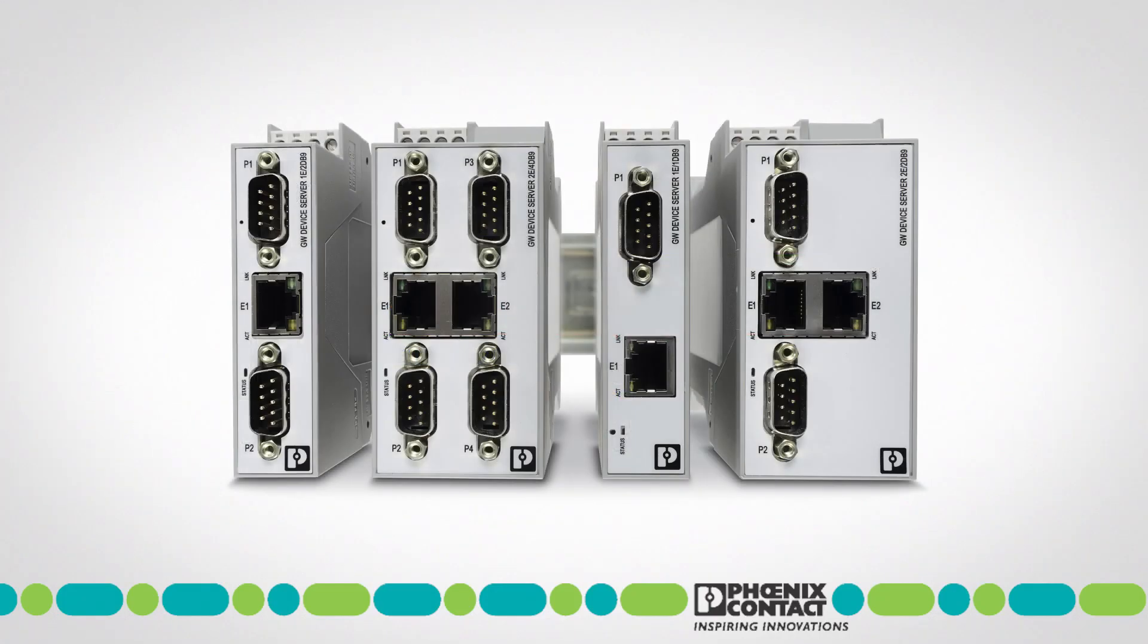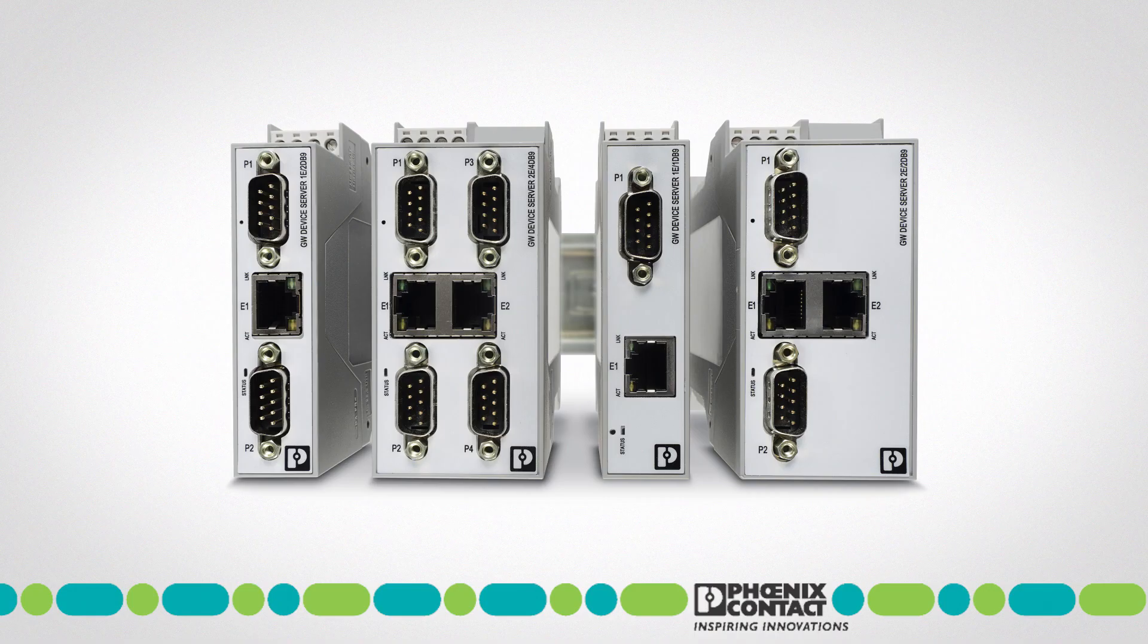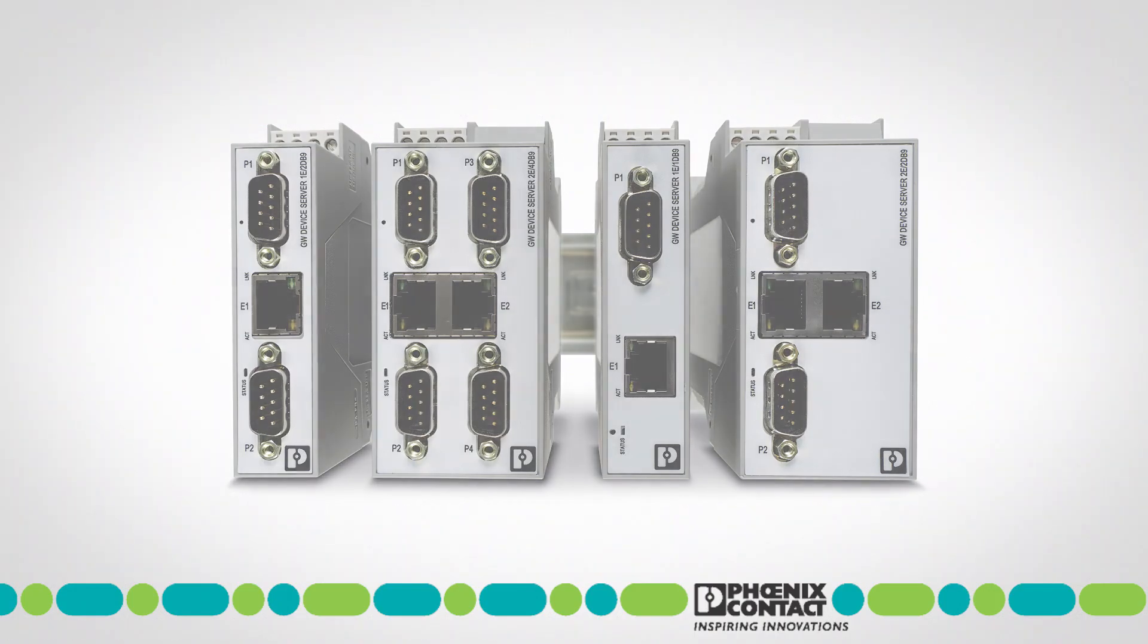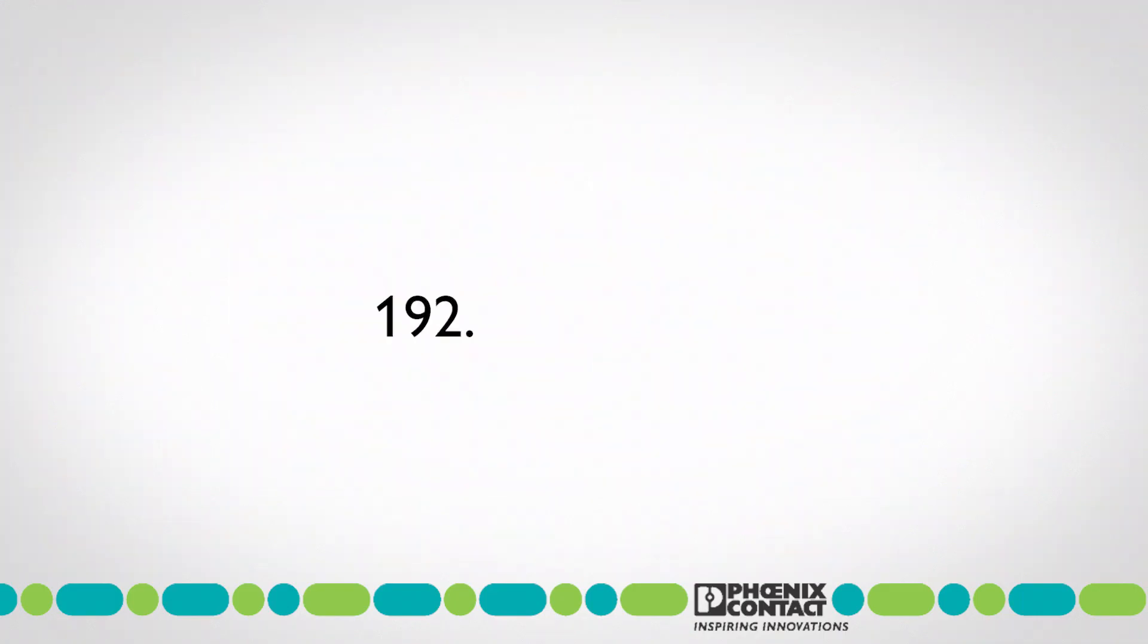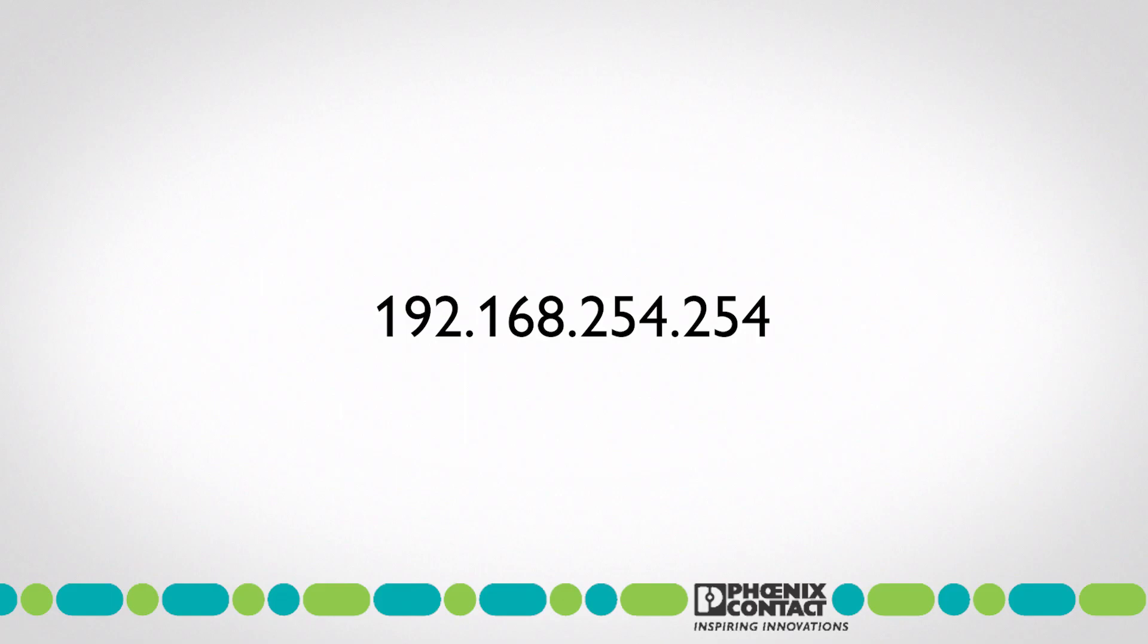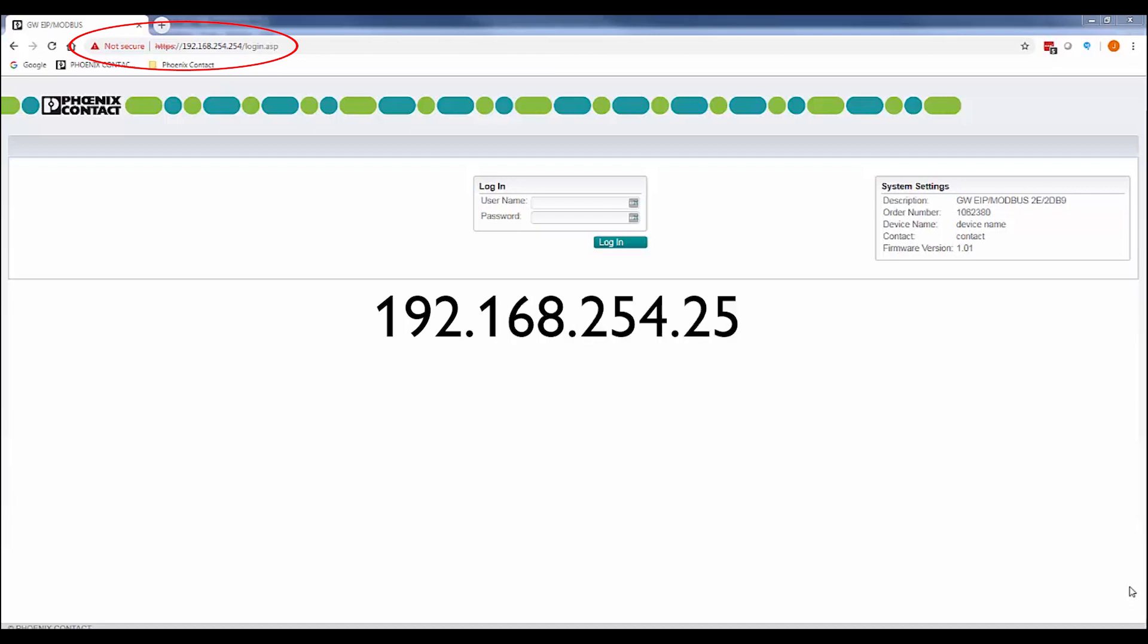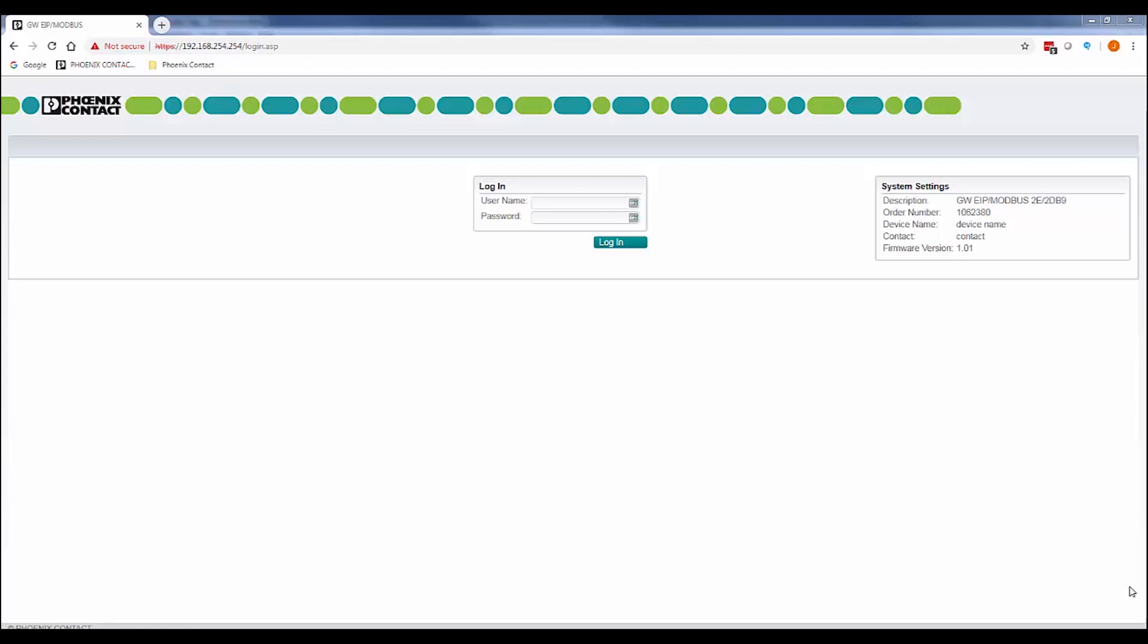First power on the gateway, then log into the unit's built-in web server. Out of the box, the gateway has the default IP of 192.168.254.254. You'll need to make sure your PC's IP address is set to this IP range before you proceed. To do this, launch a web browser and enter 192.168.254.254 in the web address bar and hit enter. This will launch the gateway's configuration.